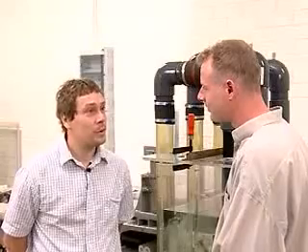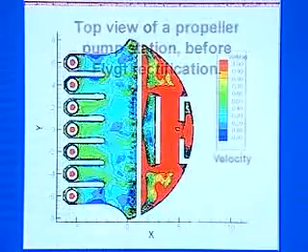There are four crucial hydraulic requirements to ensure correct flow into the pump inlet. Firstly, to prevent pre-swirl. Secondly, to minimize velocity deviation in the pump inlet. Thirdly, to avoid vortices: surface, bottom and wall. And finally, to prevent significant air entrainment. What will happen if these criteria are not fulfilled?